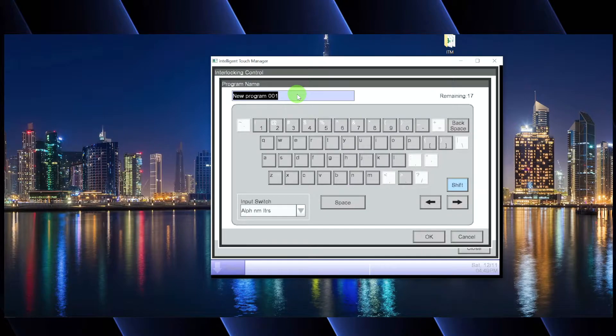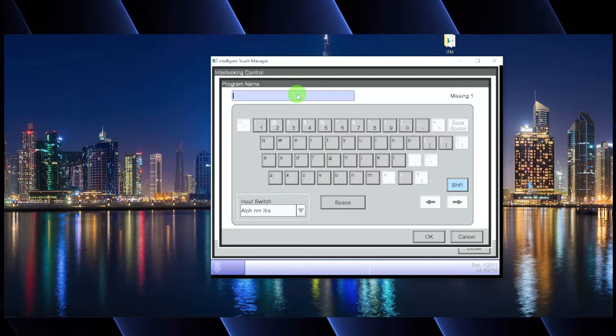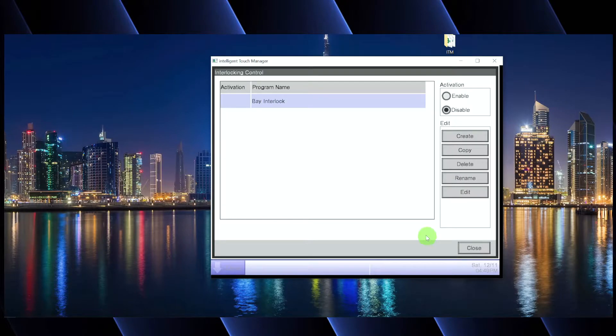So let's say we put an indoor unit into an application where humidity and temperature are sensitive. Maybe we want heat sometimes, but if the humidity and temperature get above a certain threshold, then we want to override the operation and put it into cooling. This is a hypothetical scenario because technically your indoor unit should already be monitoring its own temperature, but we're keeping this basic. We're going to click Create for our new interlock — we'll call this the bay interlock, maybe a unit out in a warehouse bay.